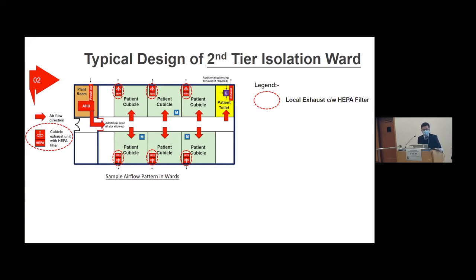In a conventional arrangement, the conversion of such a ward requires a substantial modification of the ventilation system in the general ward, by changing its configuration from a positive pressure arrangement to a negative pressure arrangement. However, such modification requires months to complete and was technically infeasible to complete within a very short period of time. Also, there was a need to revert the operation of the ward back to a general ward for future use. With the technical knowledge and experience in operating isolation wards and making reference to the designs of isolation rooms, the Hospital Authority and EMSD jointly developed a mobile air purification unit with HEPA filter for this purpose.